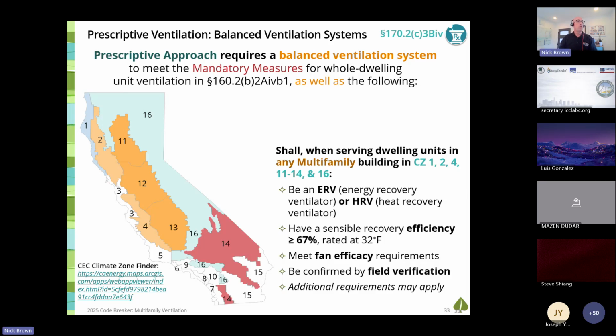No. Okay. Notice this first bullet. The energy code doesn't care whether it's an ERV or an HRV. Both have heat recovery to them. ERVs also have moisture swapping between the streams. That's the key difference. But the energy code doesn't care which is installed. But your applicants are going to get paralyzed by this decision, I promise you, and want you to help them make a decision. Supply ventilation can only be done via the performance approach because balanced is the standard.